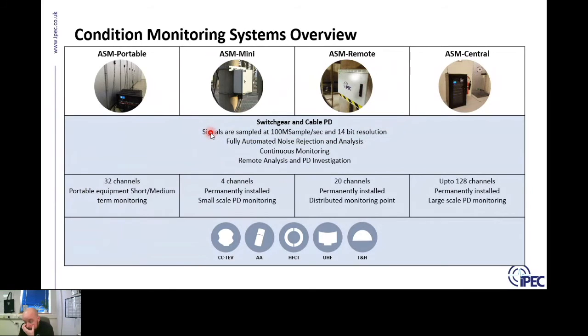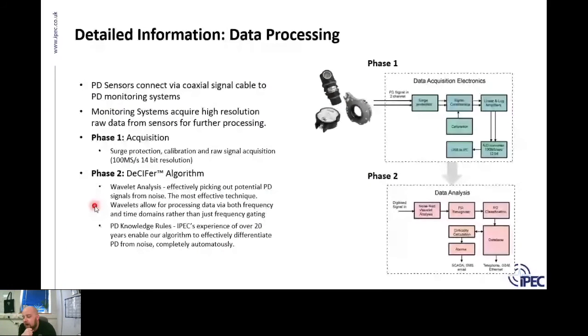The next thing we do then is our Decipher algorithm. It comes in two stages. Stage one is the wavelet analysis. Wavelet is highly regarded as the best way to pick out these sort of high frequency signals hidden inside the much larger background noise. It's a bit similar to an FFT, but it takes into account the frequency and the time domain rather than just frequency gating. A wavelet algorithm takes into account both the frequency and the time domain and sequentially processes that data to pick out these PD pulses and preserve the time elements of that so that we're able to further analyze that individual segment that's been detected. So the first phase is wavelet analysis, and what that does then is it picks out these signals that are potentially PD.